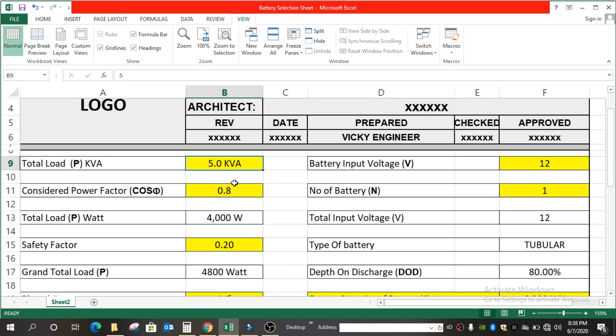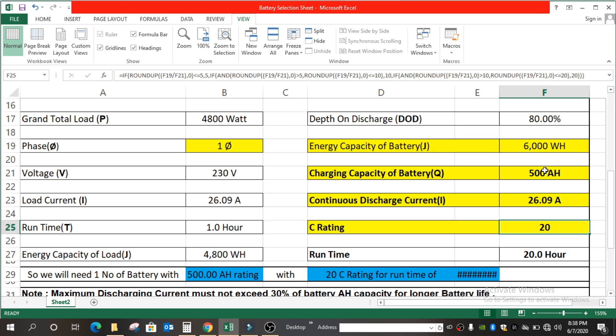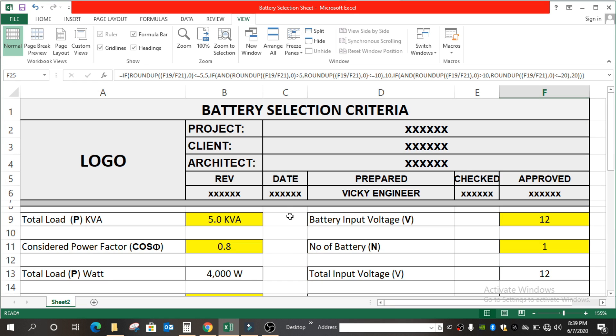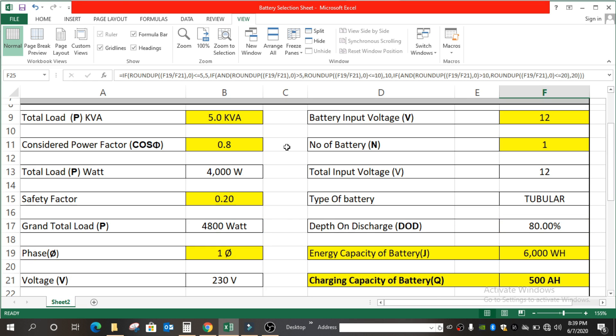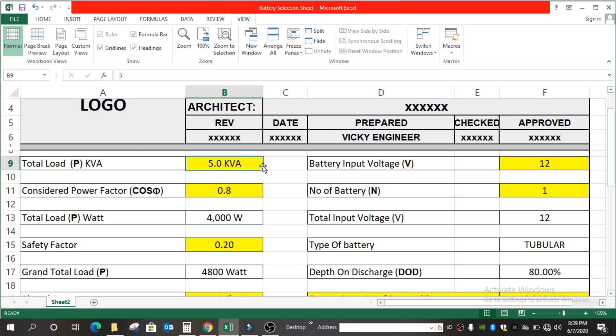You only have to enter some data in the yellow cells, so that you get the AH capacity, the WH capacity, and the continuous discharge current C rating as well. Here I have considered 5 KVA as the total load calculated, which needs to be backed up — and this value came from the UPS calculation sheet. If you don't know how to calculate UPS or haven't seen our previous video, I am giving the link in the description as well as in the card button.